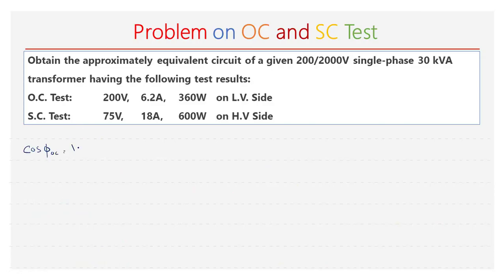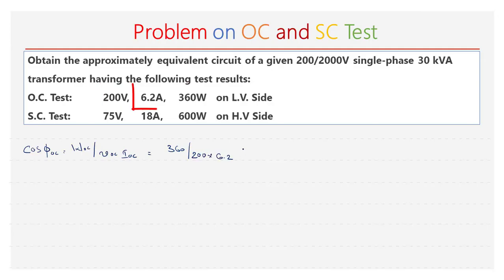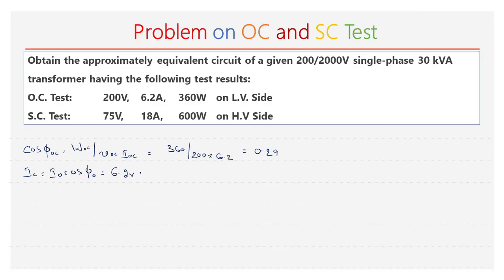Now I am going to use the same formulas for solving this problem. First, let me calculate cos φOC. cos φOC is equal to WOC divided by VOC into IOC. WOC is 360 watts, VOC is 200 V, and IOC is 6.2 A. That is equal to 0.29. And Ic is equal to IOC into cos φOC, which is 6.2 into 0.29, that is equal to 1.8 A.